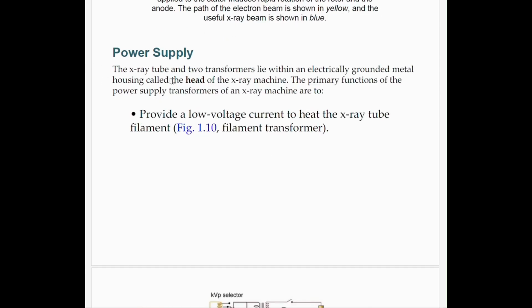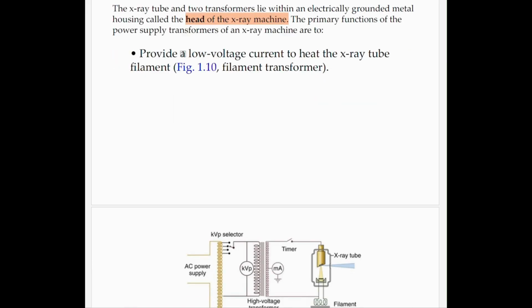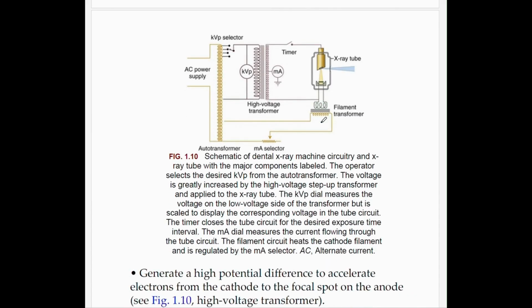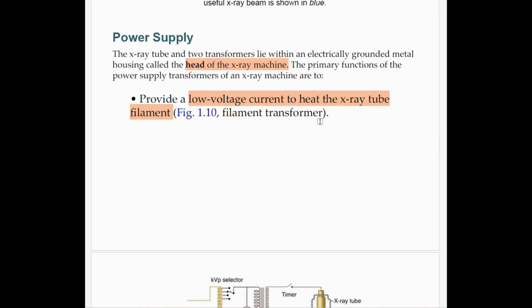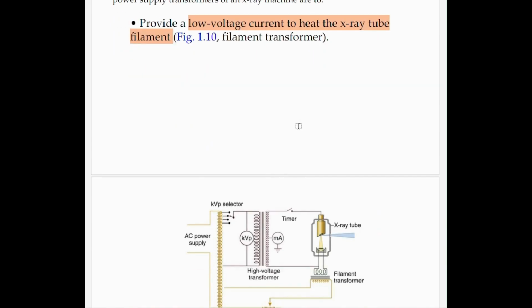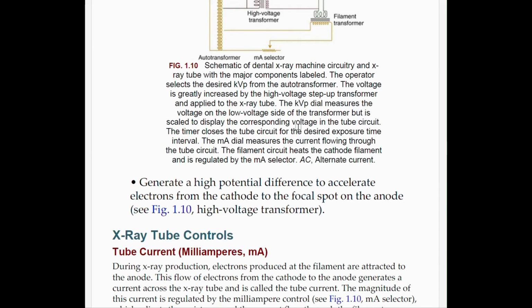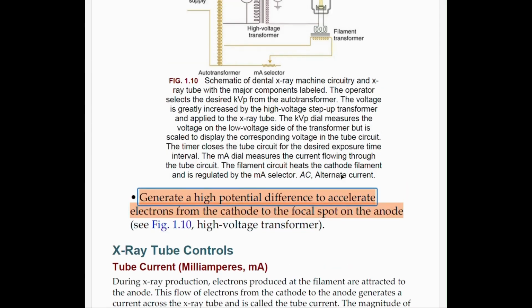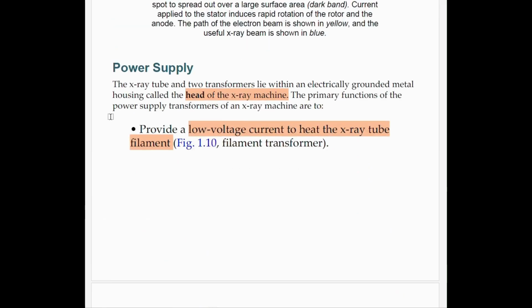Next is the power supply. The X-ray tube has two transformers that lie within an electrically grounded metal housing called the head of the X-ray machine. The primary functions of the transformers are what? They provide a low voltage current to heat the X-ray tube filament. That is the important thing about why we need a transformer, and also to generate a high potential difference to accelerate the electrons from the cathode to the focal spot on the anode. So for the power supply, there are two important things that you will mention.